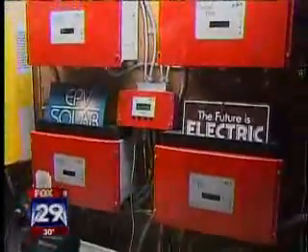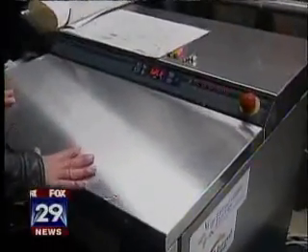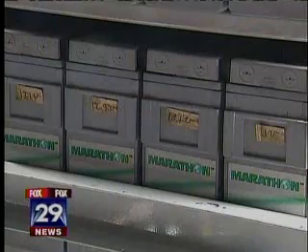The secret is a power plant of Mike Stritsky's own design that collects energy from solar panels and then stores it as hydrogen — the gas from which all those no-bill blessings flow. The solar energy comes down from the roof and goes into four inverters where it's converted into house current. Excess energy goes into a battery bank, and any excess not used in the house goes into storage by splitting water into hydrogen and oxygen through a device called an electrolyzer.